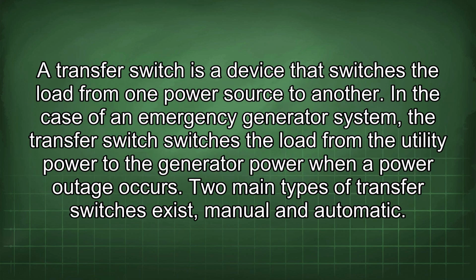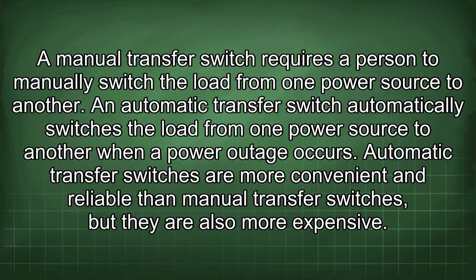A transfer switch is a device that switches the load from one power source to another. In the case of an emergency generator system, the transfer switch switches the load from the utility power to the generator power when a power outage occurs. Two main types of transfer switches exist: manual and automatic. A manual transfer switch requires a person to manually switch the load from one power source to another. An automatic transfer switch automatically switches the load from one power source to another when a power outage occurs. Automatic transfer switches are more convenient and reliable than manual transfer switches, but they are also more expensive.